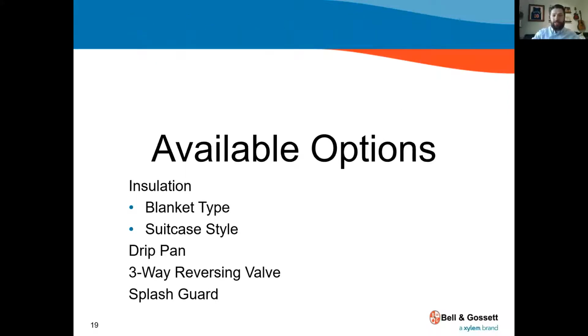Available options on your plate and frame heat exchangers. You can get insulation from factory, so they'll give a blanket type that wraps around the pack plates. Fits nice and tight. They'll cut that for you. You can also get that suitcase style. This is exactly what it sounds like. You end up with a stainless steel rectangle. It encloses the whole thing. Depending on what temperature you're bringing through it, this can be really good if you've got a very hot or a very cold medium that requires insulation. You can put a drip pan for the same reason.